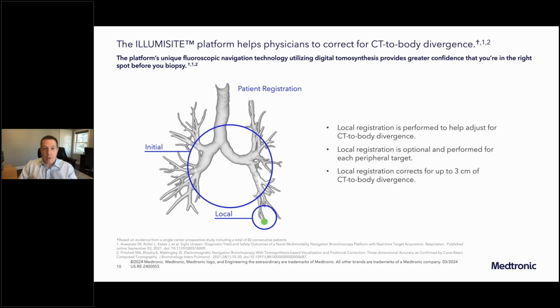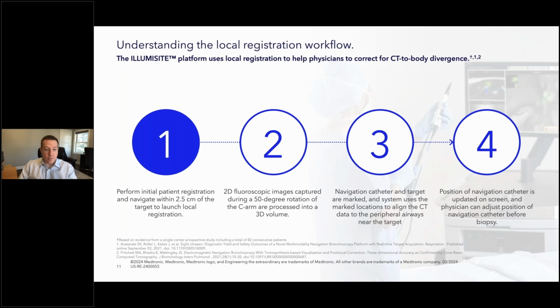The ILLUMISITE platform really does a nice job helping you to correct for the CT to body divergence because it introduces something called local registration. Local registration is optional. It's done after the initial registration, and it's performed for each peripheral target, but it has the ability to correct for divergence up to 3 centimeters. And particularly in the lower lobes, where divergence can be on average 2.5 centimeters, this is critical. So here's the local registration workflow.